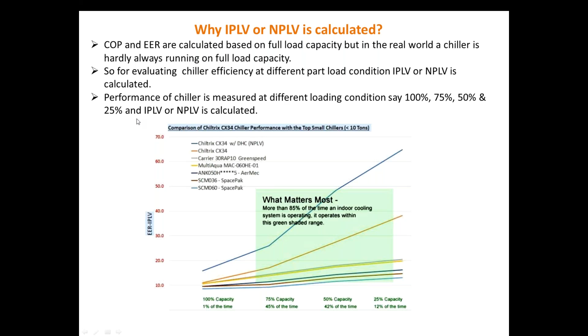As I told you, IPLV and NPLV are calculated for part load performance. Part load energy efficiency is calculated at 100%, 75%, 50%, and 25%. So these four load points are fixed, and the values of COP at these four points are, for example, A is COP or EER at 100%, B at 75%, C at 50%, and D at 25%. With the help of the formula, IPLV or NPLV is given as 0.01A plus 0.42B plus 0.45C plus 0.12D. So this is the formula to calculate IPLV.